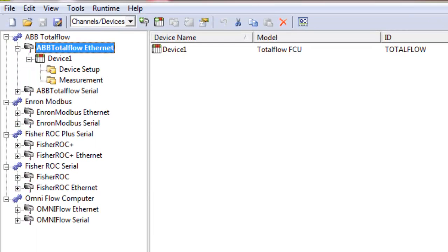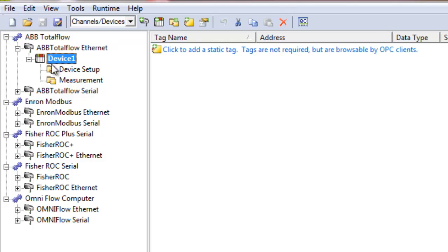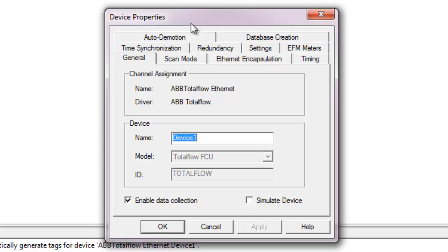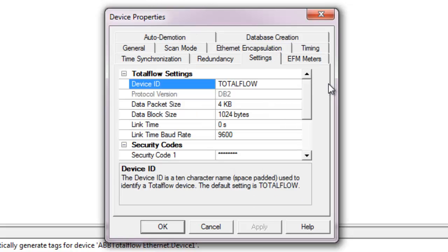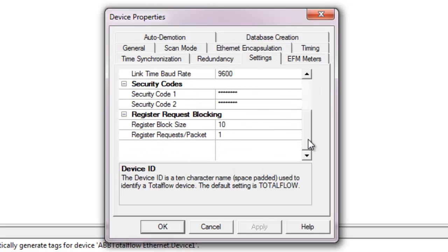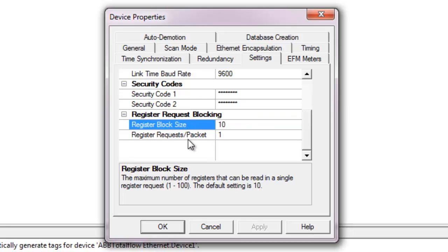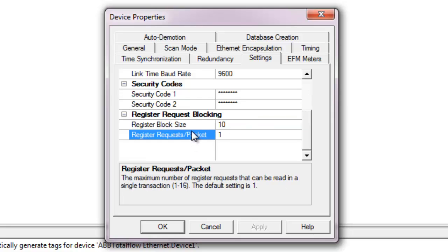ABB Total Flow devices have several unique settings different from other flow devices. And our driver needs to know how these settings are configured for proper device communication. In the settings tab located in the device properties window, the user can optimize communication with the device using register request blocking. Register blocking is controlled with two settings in the driver, register block size and registers request per packet.